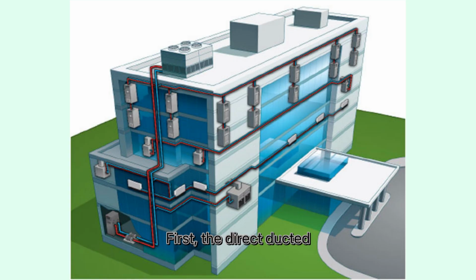When it comes to bringing outdoor air into a WSHP system, there are two common strategies. First, the direct ducted outdoor air method. In this approach, outside air is ducted straight into the occupied space. While this method is simple, it often causes discomfort for people sitting near the diffusers. The unconditioned air can create drafts or uneven temperatures, making it less desirable in most designs. So generally, this option is not preferred.